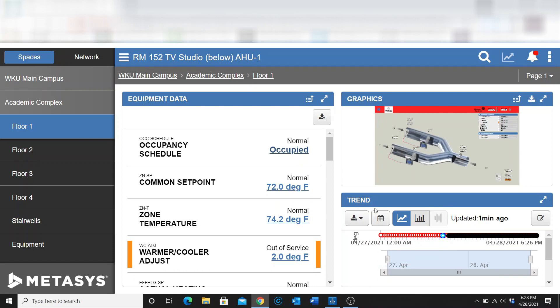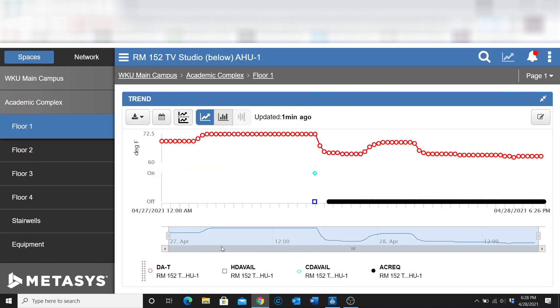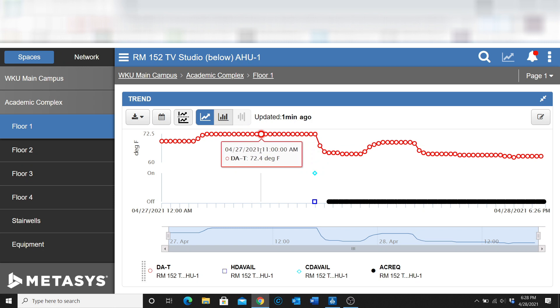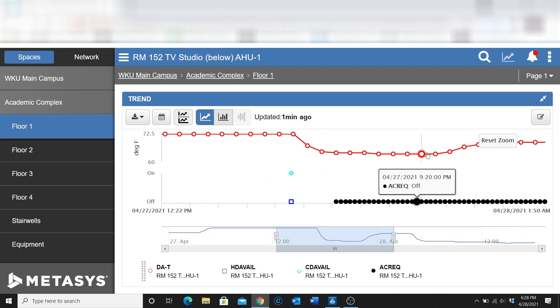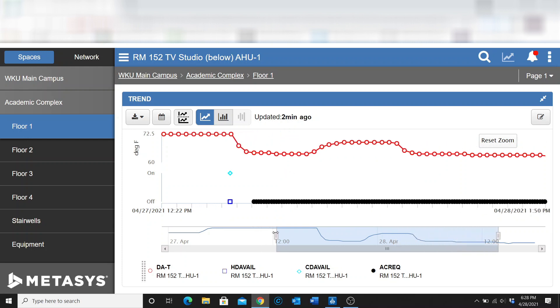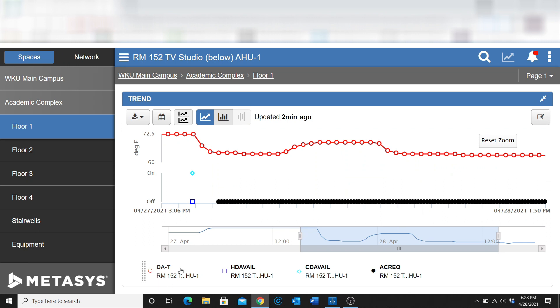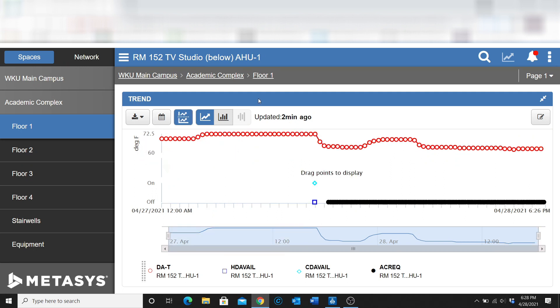I can also go in and add an attribute and annotation — as far as why a change has been made, you can set up a preset for your change — all from this one screen. Down here on the right you can see where the trends are. This is another neat feature. I'll expand that out and I can see all of the trends associated with this particular VAV. I can hold my mouse to a point, click, hold, and drag to zoom in on that trend.